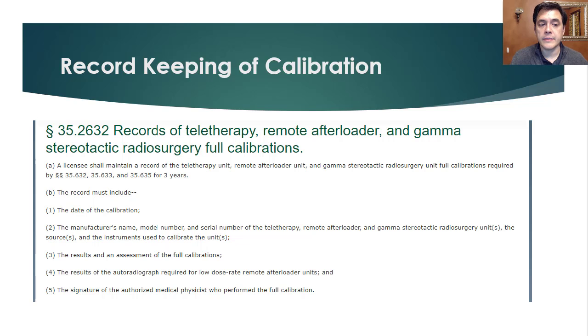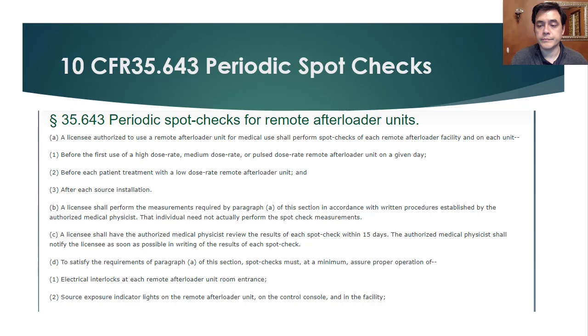Continuing on. CFR 35.643, periodic spot checks. So before the use of a high dose rate applicator on any given day and after each source installation, there is a spot check of the entire system. This could be combined with the calibration measurement, but it is in addition to, for certain.